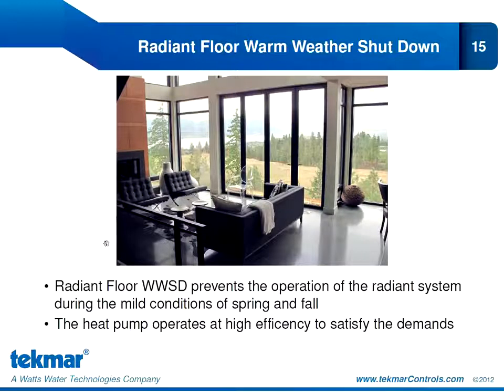Radiant floor warm weather shutdown is another new setting for Tekmar, particular to the 557. To explain this setting, let's look at the image we have on the slide, and let's assume this is a west-facing home. We can see there is a lot of window area here. There's actually 2 levels of floor-to-ceiling windows. So we can expect that this room is probably going to have a significant solar gain in the afternoon. In the shoulder seasons, though, the mornings are probably quite cool while the afternoons are still warm.